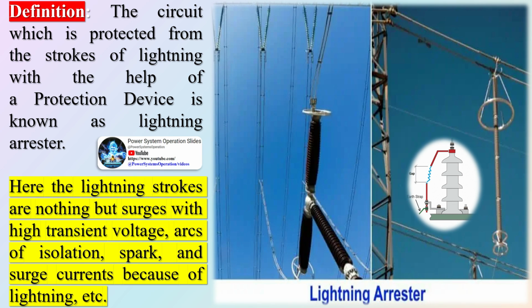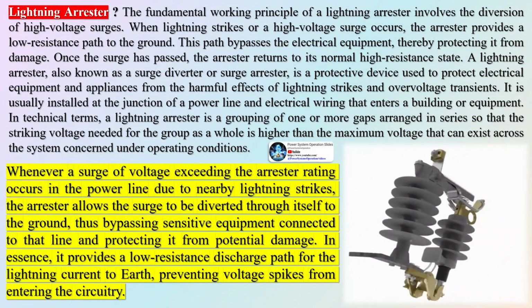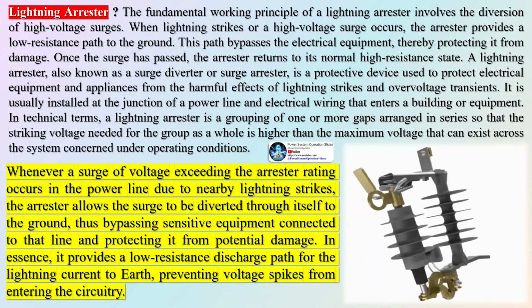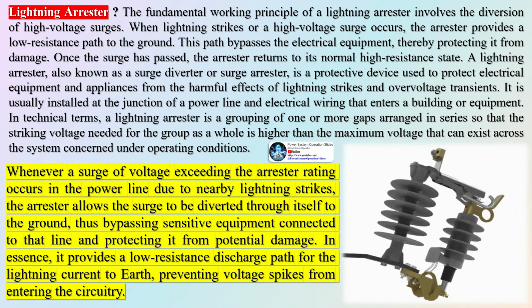The fundamental working principle of a lightning arrestor involves the diversion of high voltage surges. When lightning strikes or a high voltage surge occurs, the arrestor provides a low resistance path to the ground. This path bypasses the electrical equipment, thereby protecting it from damage. Once the surge has passed, the arrestor returns to its normal high resistance state.